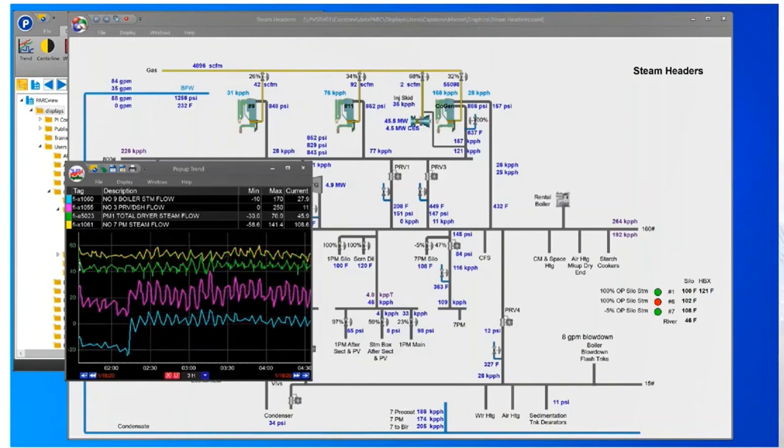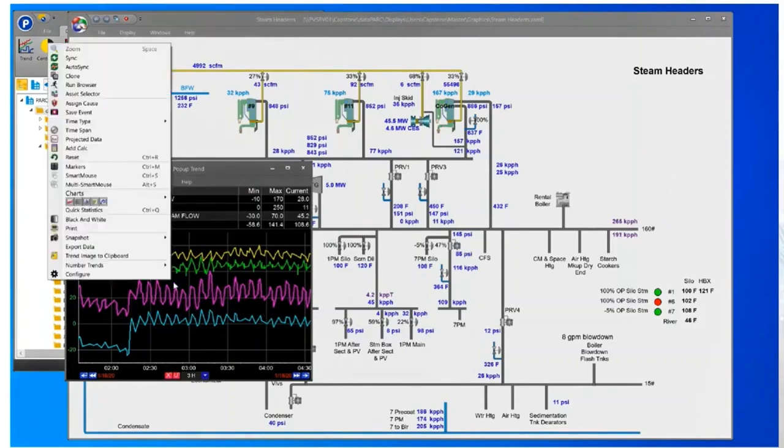They are exactly on top of each other, and it's the same issue. It can't be a coincidence that they're on top of each other. They can't have something internally that both of them are just magically having this oscillation at the same time. So most likely, the conclusion, if we're going to look farther, is that we're going to look at the controller, the PRV controller, as it seems more obvious that that's the thing that's the problem.